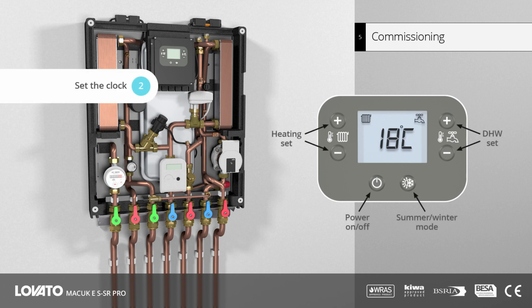Step 2 in commissioning the system is to set the clock. Press the heating plus and minus buttons simultaneously and using the DHW Plus button, press to select the hour value. Press the Summer/Winter button and repeat the process for the minutes value. Finally, press the power button to exit the clock setting mode.